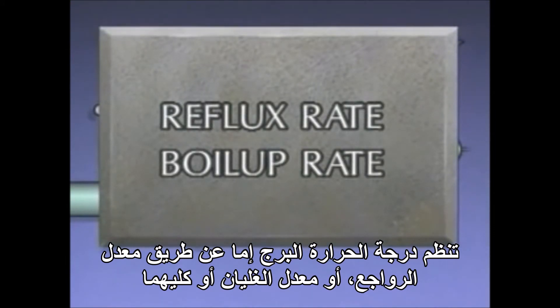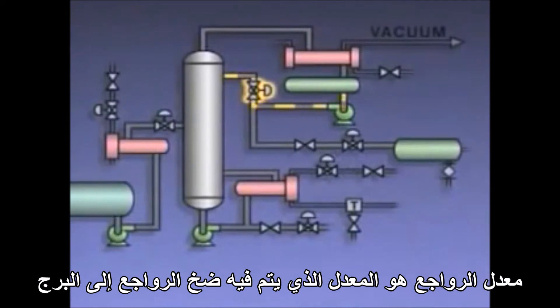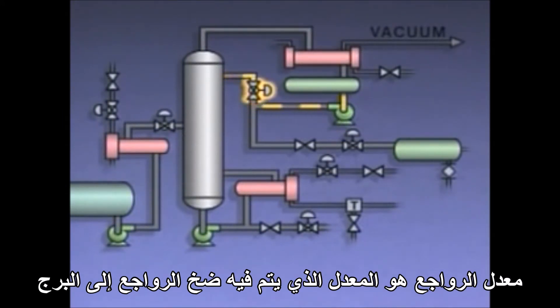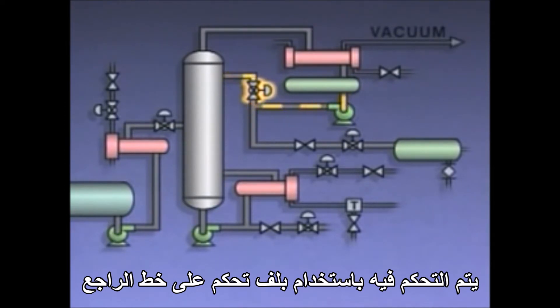or both. The reflux rate is the rate at which reflux is pumped to the column; it's adjusted using a control valve in the reflux line. The boil up rate is controlled by adjusting the steam flow to the reboiler.